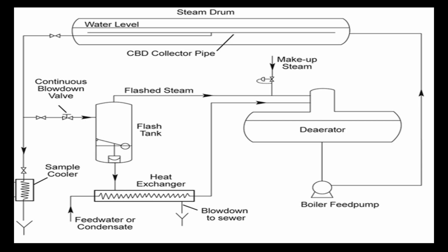The other interesting thing in this diagram is that on the line coming out of the steam drum, we also can see here that we have a sample cooler going down to waste. And that's simply where we'll take our samples for regards to things like our water tests. And that sample cooler will simply be cooled against cooling water or maybe just simply utility water.